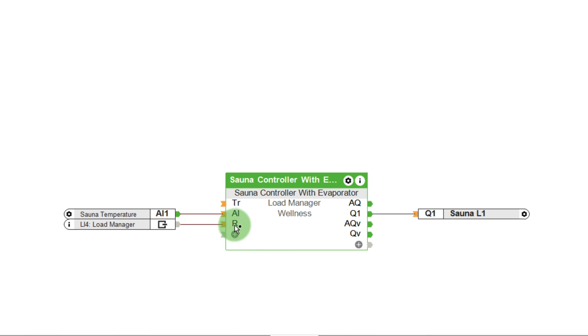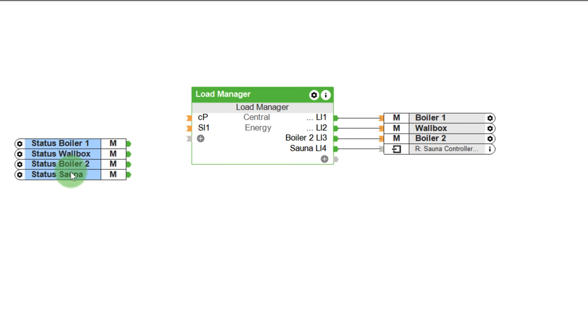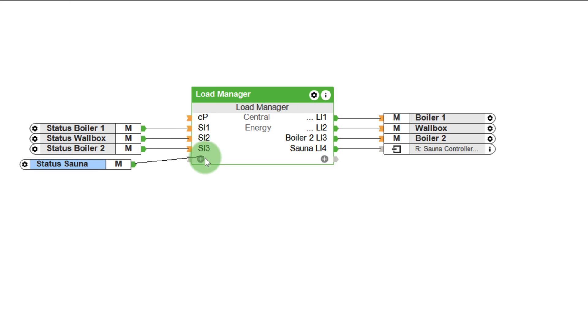For example, the output responsible for the load shedding of the sauna is connected to the R input of the sauna block. If the load manager disconnects the sauna in the event of an overload, the sauna function block is locked and the app displays why it is currently not available. The status of the electrical devices is determined via the status inputs of the function block. The status inputs are not mandatory; however, the status is displayed in the Loxone app when using the inputs. On top of that, you will be notified if the device is disconnected due to a potential overload.